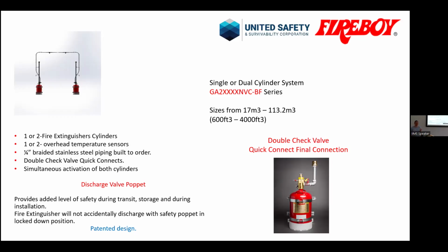The reason for that is that the connecting link is also pressurized, and both of the valves are pressure differential valves. So basically, if one of them goes off, or if you lose the pressure in a link, it'll set off both of the cylinders at the same time. So that allows you to split the volume of the gas between the two, because it will still go off at the same time, under 10 seconds. That's the only time we recommend fitting, or allow fitting, 2 cylinders within the same space.